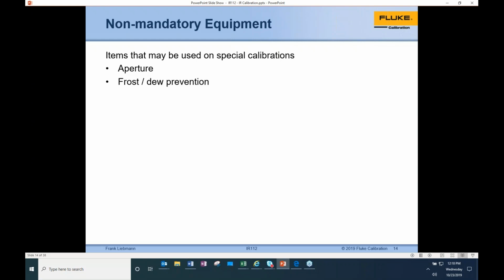On our 4180 unit, the target cover has a dry air purge system built into it, where you can take either dry shop air or dry nitrogen, run a tube over to it, and connect it. With a very low volume, just enough to get positive pressure, it'll bleed through and keep positive pressure on that target, preventing frost, versus if you were to pull it off and run at, say, 5 degrees C in a 20 degrees C room. So things there can be done.